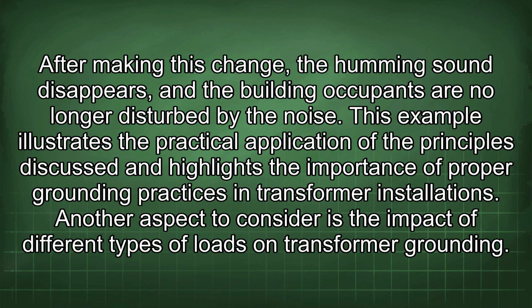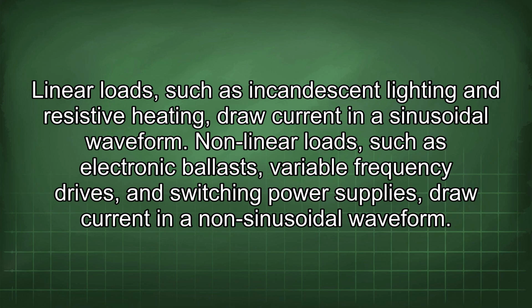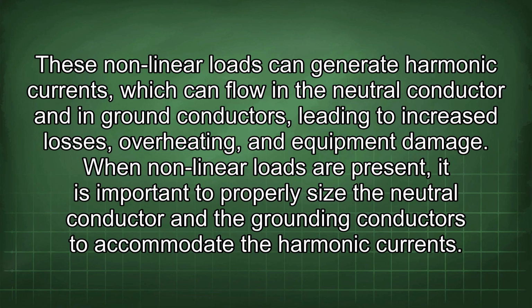Another aspect to consider is the impact of different types of loads on transformer grounding. Linear loads, such as incandescent lighting and resistive heating, draw current in a sinusoidal waveform. Non-linear loads, such as electronic ballasts, variable frequency drives, and switching power supplies, draw current in a non-sinusoidal waveform. These nonlinear loads can generate harmonic currents, which can flow in the neutral conductor and in ground conductors, leading to increased losses, overheating, and equipment damage.